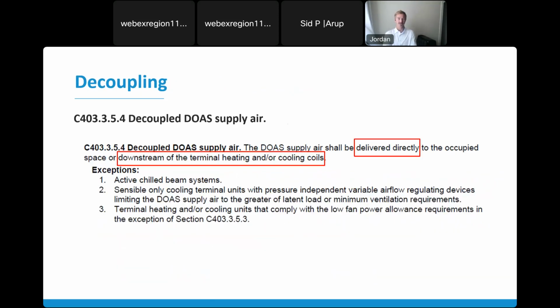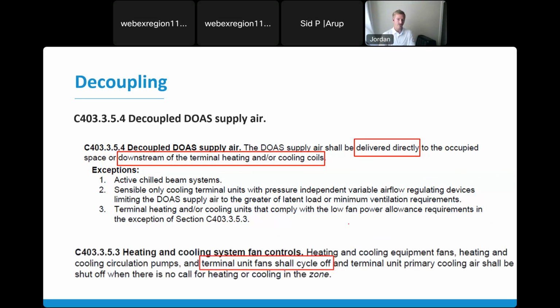And then decoupling. So how is ventilation air delivered to the space? This is the Washington State Energy Code. The DOAS supply shall be delivered directly to the occupied space or downstream of the terminal heating or cooling units. Exceptions: chilled beams, sensible only cooling units with pressure independent airflow, and terminal heating and cooling units that comply with the low fan power.